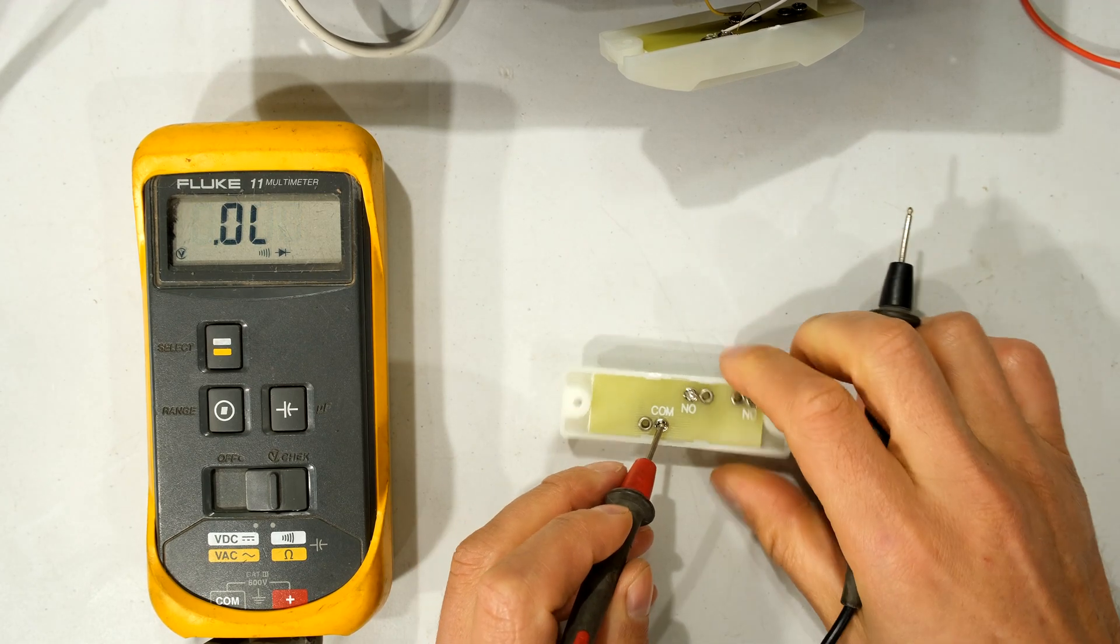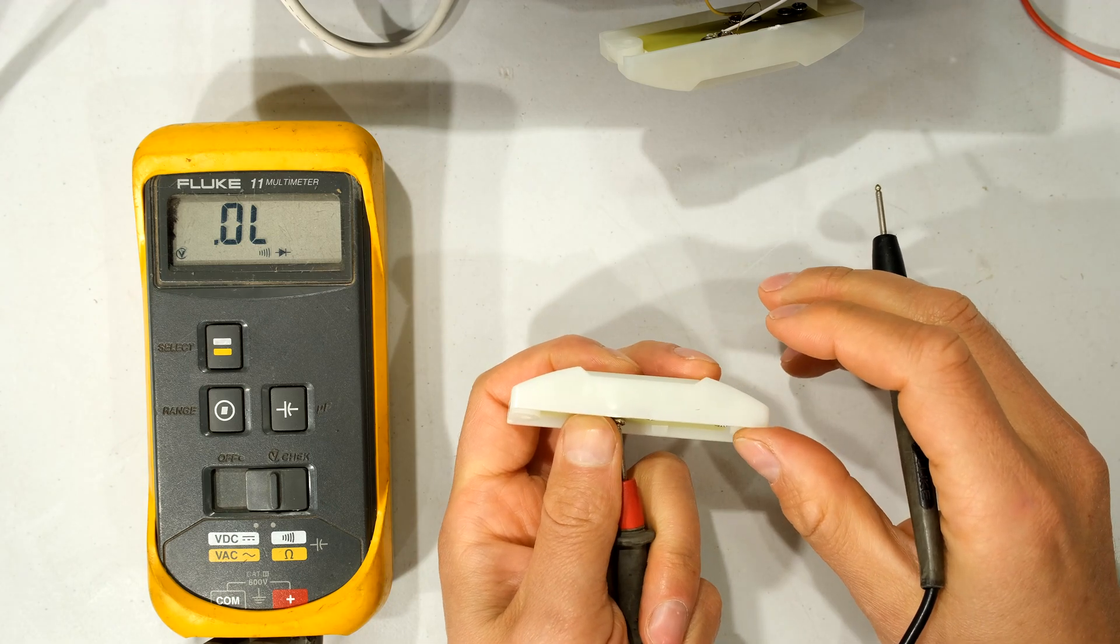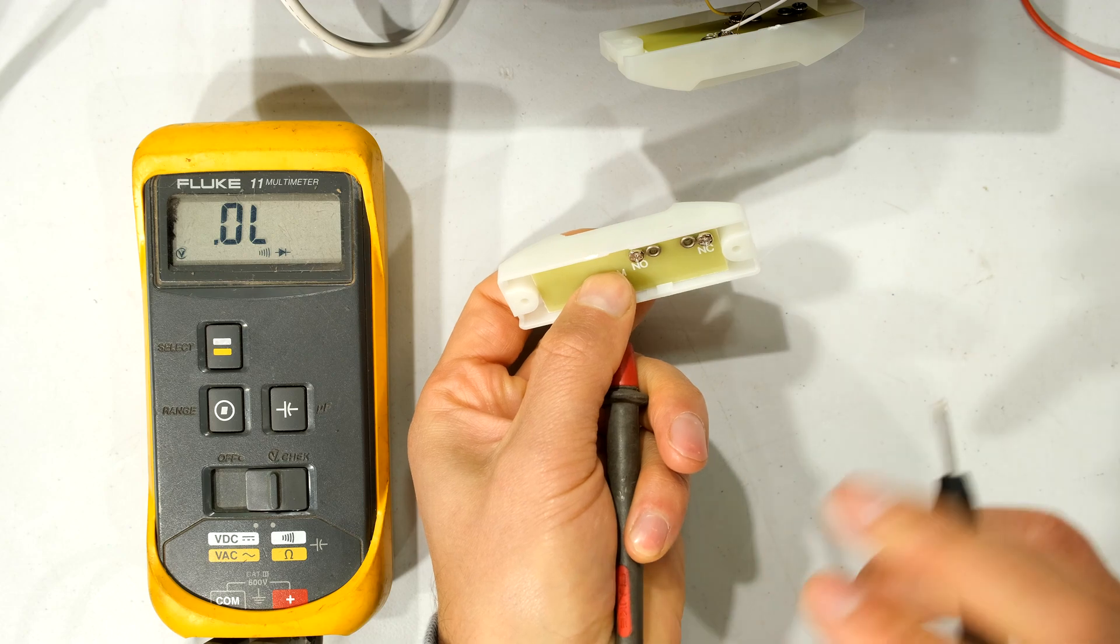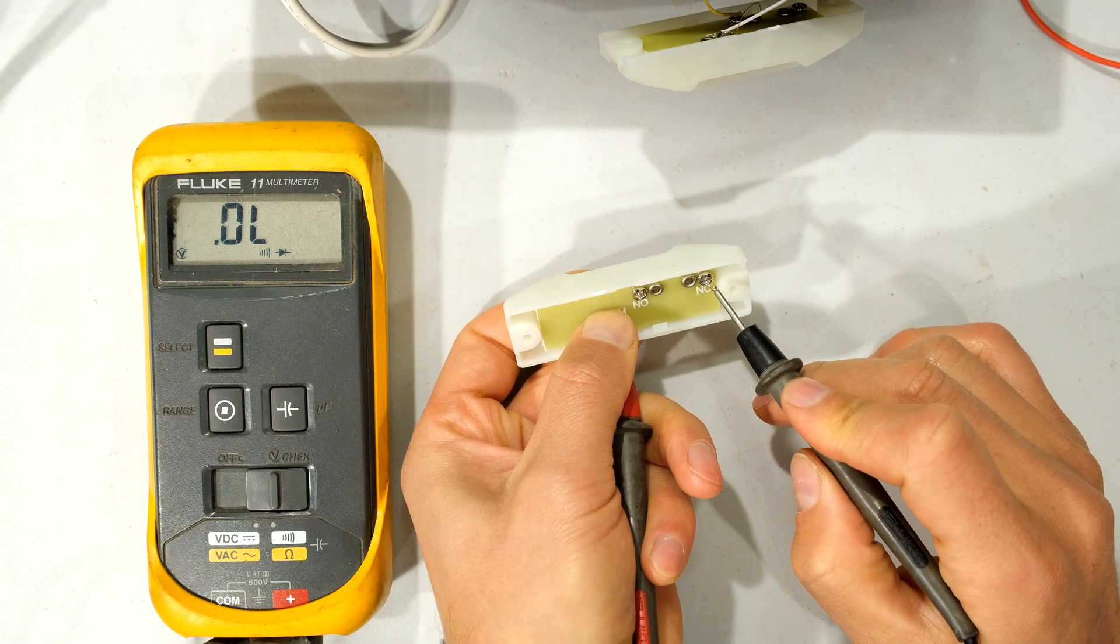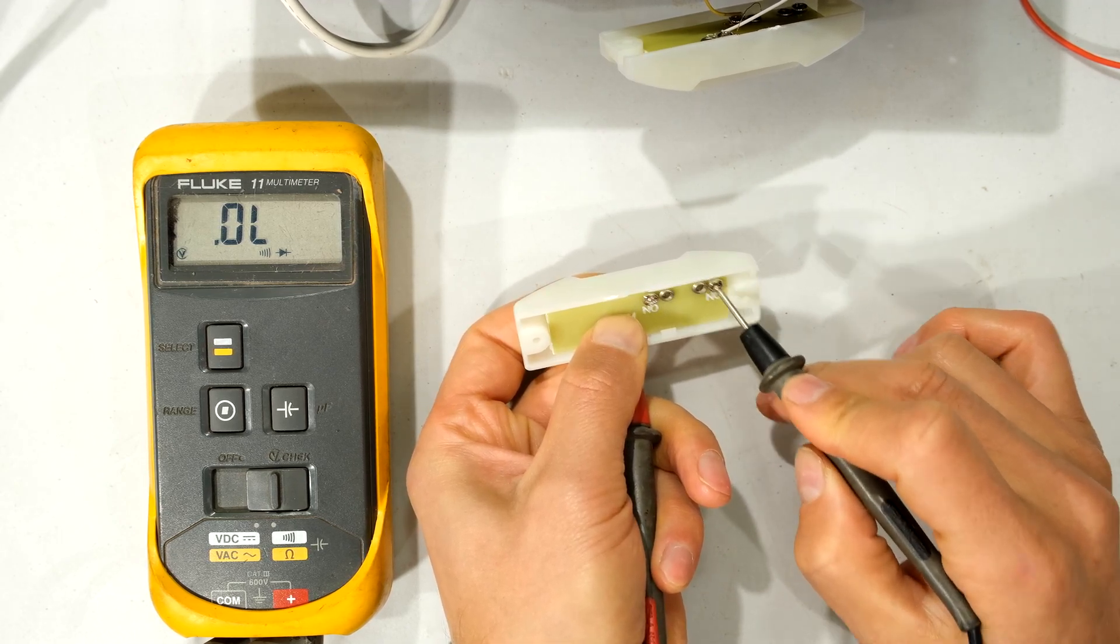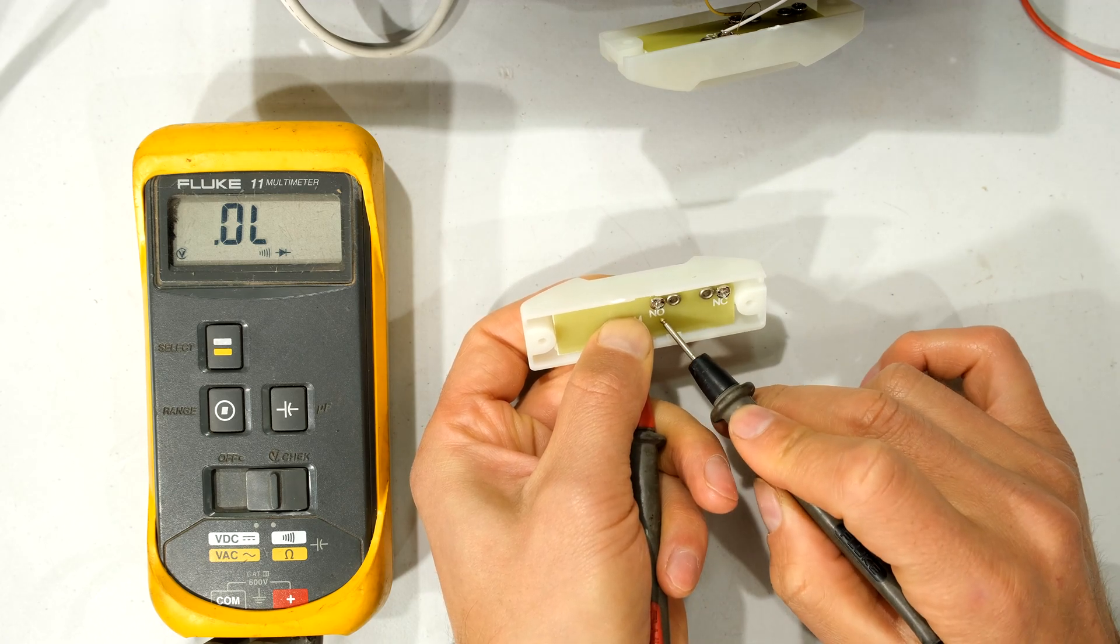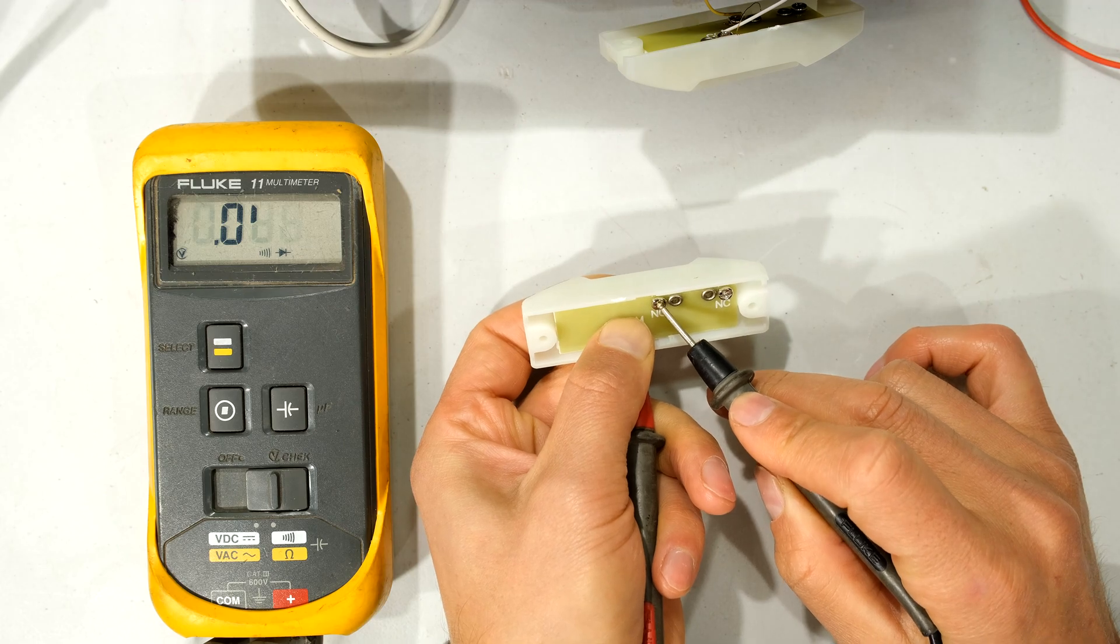But if I depress the button now I'm depressing the button. So the button is now depressed and now when I put my other lead on the NC look it is now open circuited. So by pressing the button I've changed the state from normally closed to open and the normally open which was an open circuit now becomes closed.